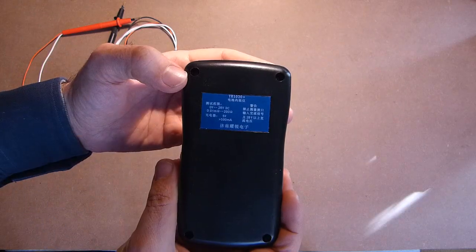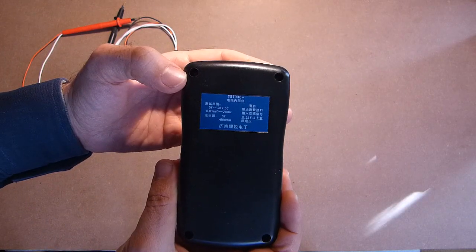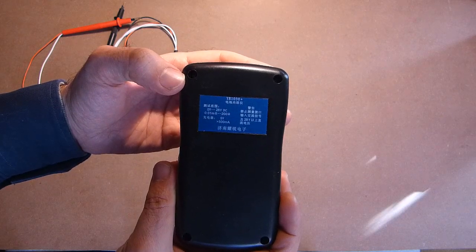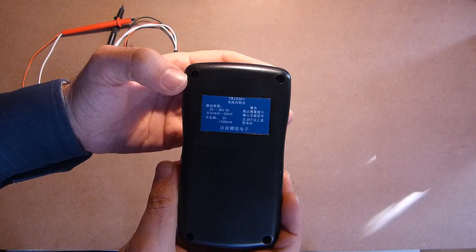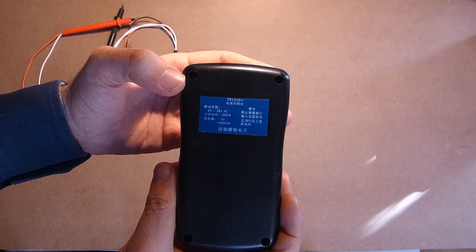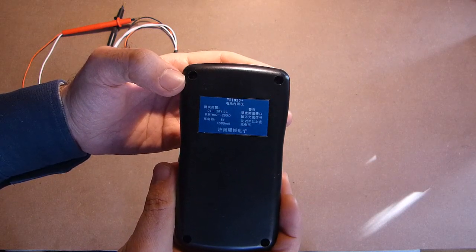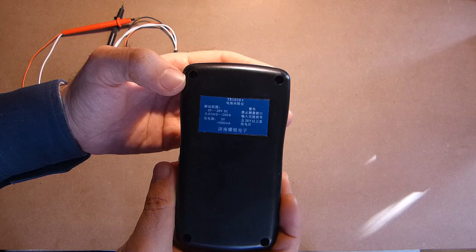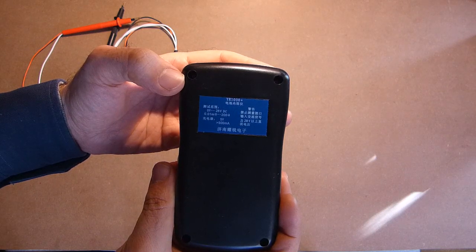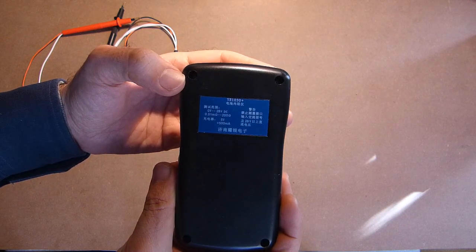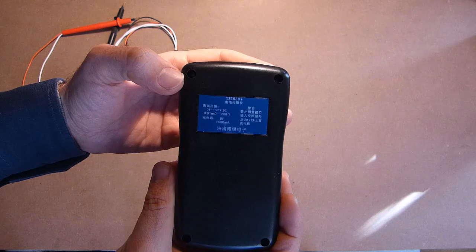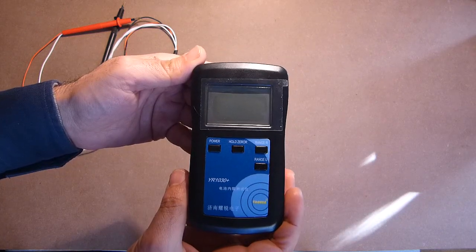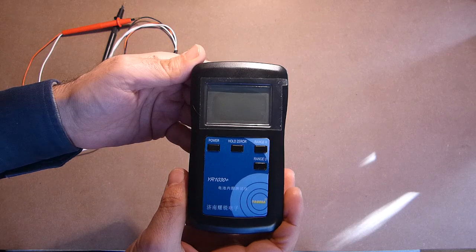Here we see the name of the device, YR1030+, the voltage range from 0 to 28 volts, and impedance range from 0.01 milliohms up to 200 ohms. The power supply used for charging should provide 5 volts and more than 500 milliamps. This version is in Chinese, but anyway let's turn this device on and see its menu.